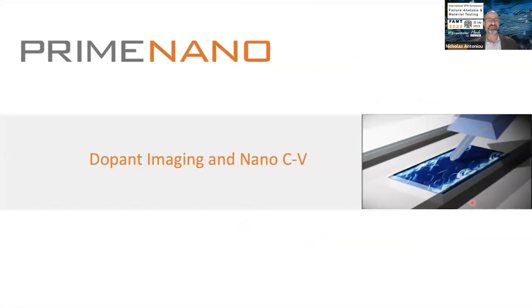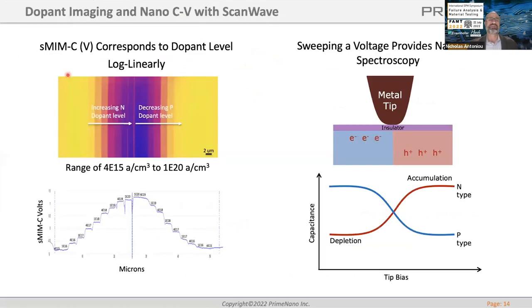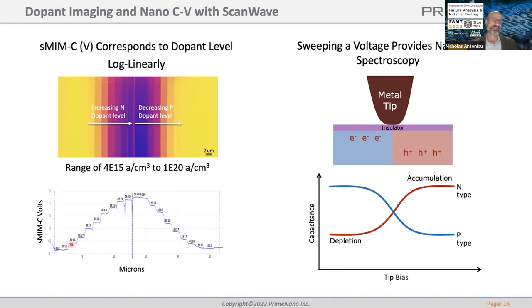Now into dopant imaging and nano-CV. This is an implant reference sample we provide in our quantification product. There are 10 dopant levels of n-type in a staircase from about 1E15 up to 1E20, and adjacent to that are 10 p-type doped regions in a staircase from about 1E20 down to 4E15. We use this for quantifying dopant levels. You can see the capacitance response to different dopant levels — our system outputs volts for both resistance and capacitance.